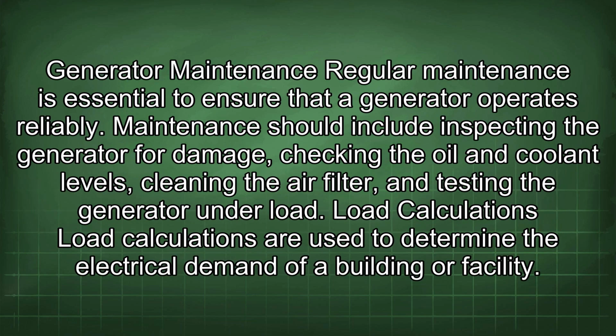Generator maintenance. Regular maintenance is essential to ensure that a generator operates reliably. Maintenance should include inspecting the generator for damage, checking the oil and coolant levels, cleaning the air filter, and testing the generator under load.